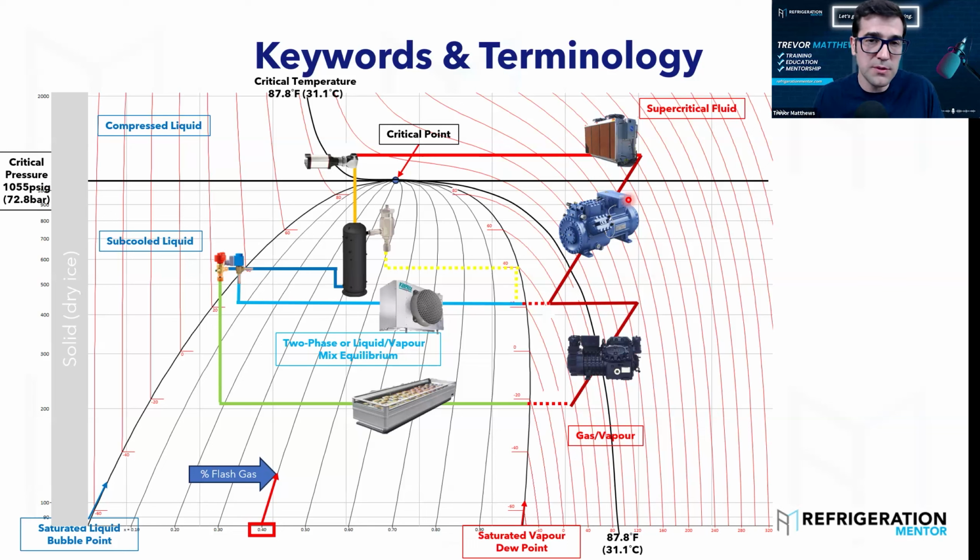Because I see multiple times technicians come into the program saying, I kind of understand the sequence of operation. Well, no, there's no kind of. Let's understand exactly the way it's supposed to work, so you understand when a problem happens. I have an oil issue because that receiver is going up and down. The temperature is going up and down, or the pressure, however you want to call it. It goes up and it goes down. That is going to change the effect on a certain design. So if you're using an oil receiver or oil vessel pressure, and you're running your receiver at the flash tank pressure, your flash tank's all over the place. What is happening in that receiver?